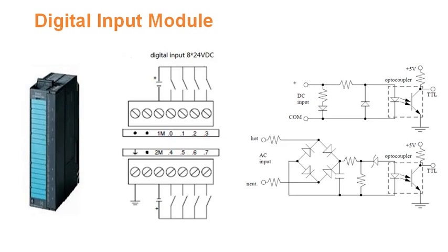If your input is of 230 volts or 110 volts AC, then we have to select the digital input module which accepts this AC. Internal to this digital input module, there will be a rectifier which converts this AC to DC, and then further it applies to the opto transistor.